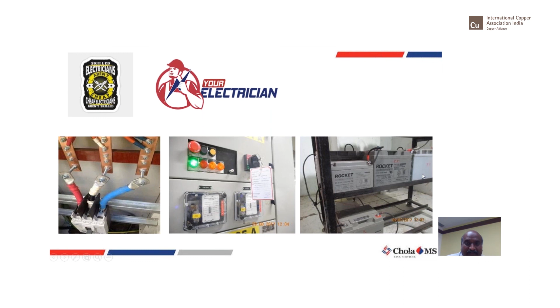Facility management people, please have a look at the cables and the battery racks that you are using in your facilities or offices. Please do not have more than two different battery makes, ages, or capacities in the same bank. It is the first bomb which is going to explode in your facility. These are much more dangerous. Replacing one dead battery without matching the age or the manufacturer, say one is Rocket, one is Panasonic, one is USA batteries, so trying to mix up the batteries is also highly dangerous. Each one has its own characteristic curves for the charging and discharging cycle.